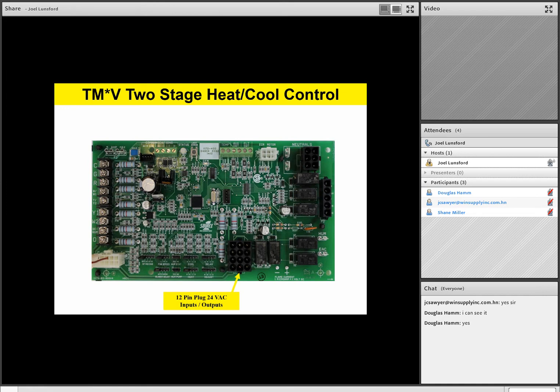So you have one set of jumpers called delay. The delay jumper is to adjust your cooling. This is a cooling on delay, so maybe make a note of that. This is a cooling on delay. And the jumper selection is A, B, C, and D. Now that has to do with geography. And what I mean by that is this.